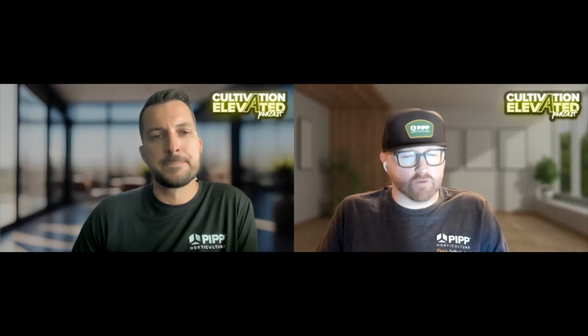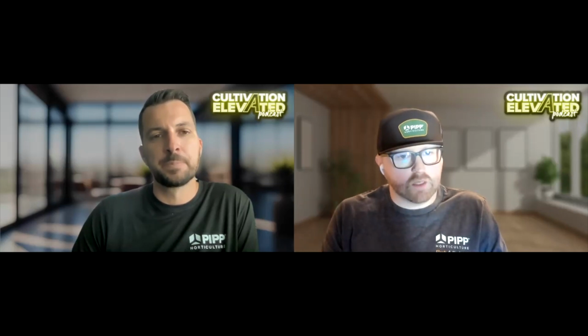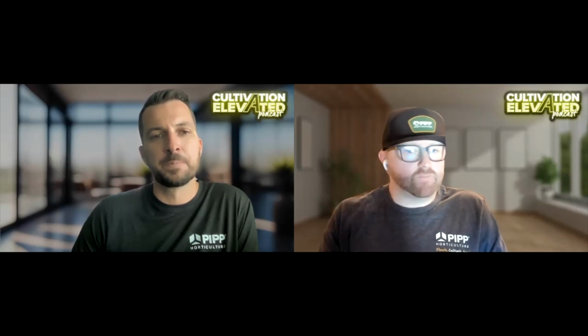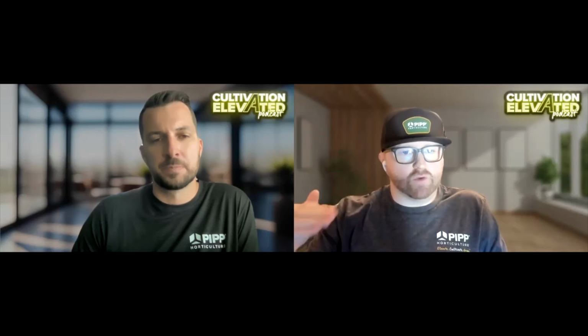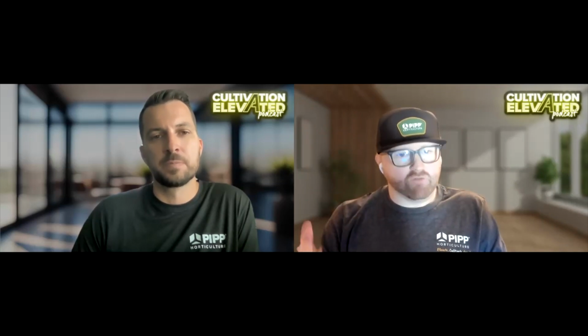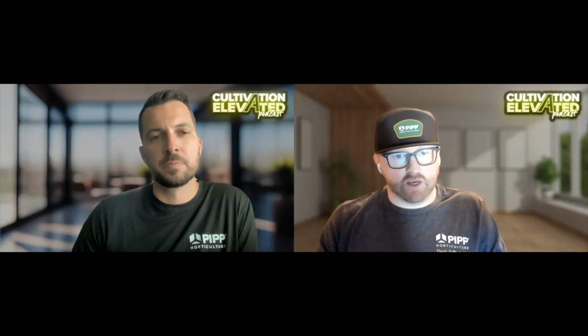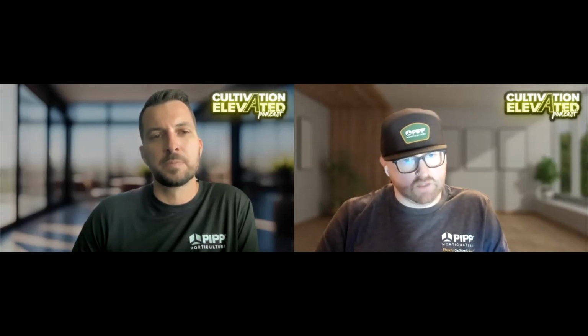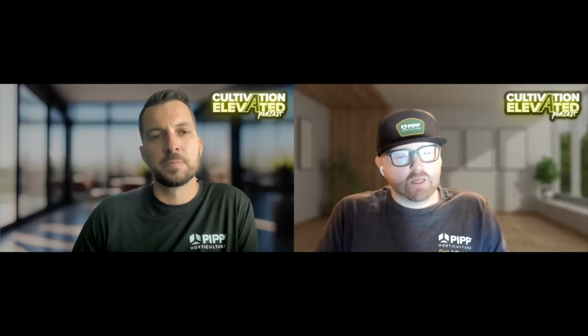That does remind me of one other point though. With our new VAS 2.0 airflow system, it's putting out over double the amount of air 3 feet below the duct compared to the original system. So it's putting out a significantly higher air velocity further down, with a further throw into the canopy. We have data at the duct at 1, 2, 3, and 4 feet below, every foot, for every single configuration we would ever sell. So we know how that system will perform, how far it'll penetrate, and what velocities it'll produce.